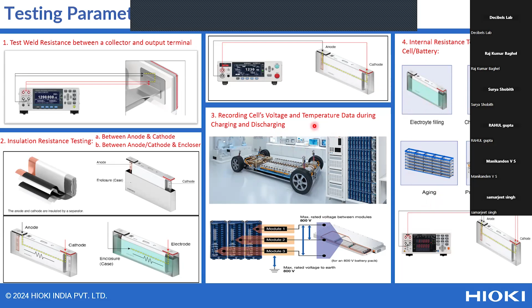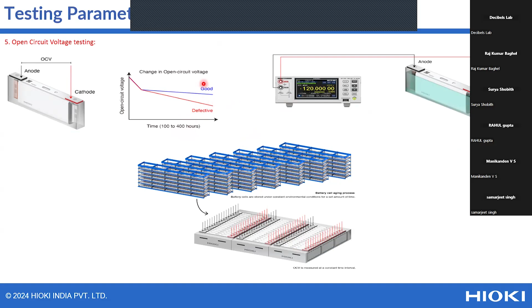to 400 hours, and then after that you check the voltage by using a Hioki DC precise voltmeter, and you check how much the voltage has dipped. If it is reduced below a particular limit, then we reject the cell or battery. So by using a voltmeter you can also check this quality, open circuit voltage.